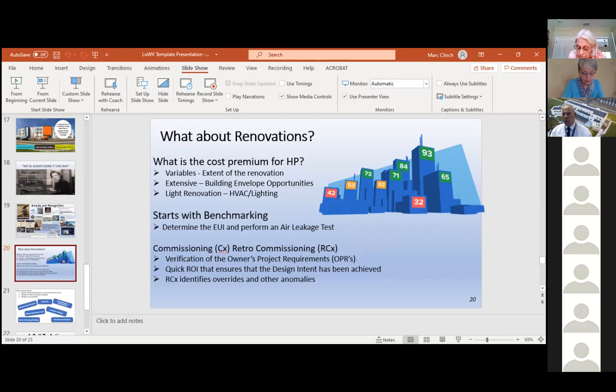I'm also a believer in commissioning and retro commissioning. Commissioning on new buildings is the verification of the owner's project requirements. Just because you have a design and a mechanical contractor doesn't mean you're necessarily going to get that intent. You have to trust but verify, and we do that through commissioning. So I don't look at commissioning as an additional project cost, I look at it as an investment, because we always find that what we discover through the commissioning process is well worth the dollars we spent on it, ensuring we're getting the ROI we should be.